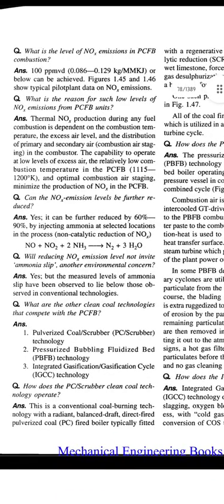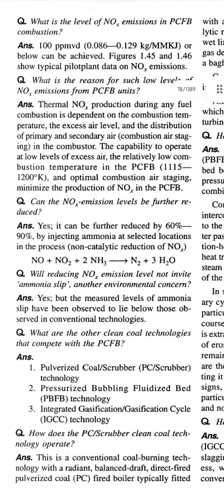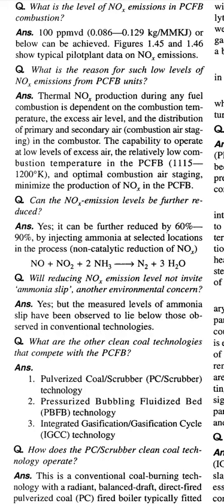Question: What is the reason for such low levels of NOx emissions from PCFB units? Answer: Thermal NOx production during any fuel combustion depends on the combustion temperature, the excess air level, and the distribution of primary and secondary air — combustion air staging in the combustor. The capability to operate at low levels of excess air and the relatively low combustion temperature in the PCFB (1,115 K to 1,200 K), along with optimal combustion air staging, minimizes the production of NOx in the PCFB.